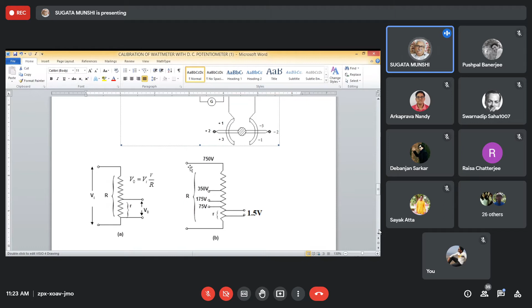Now here, if you use the potentiometer to calibrate the wattmeter, what is the simplest possible arrangement? Let me just point out. This is the wattmeter current coil. The potential coil or voltage coil is here, in series with a high resistance. So all these things are there inside the wattmeter. We don't have access to those things. We have access to the two terminals of the current coil and the two terminals of the potential coil.